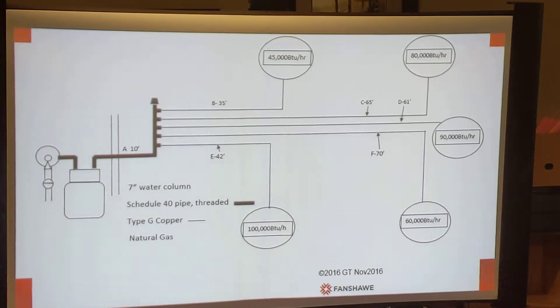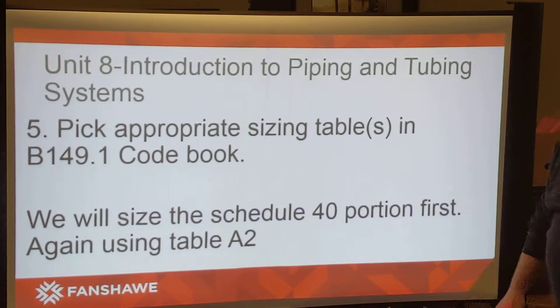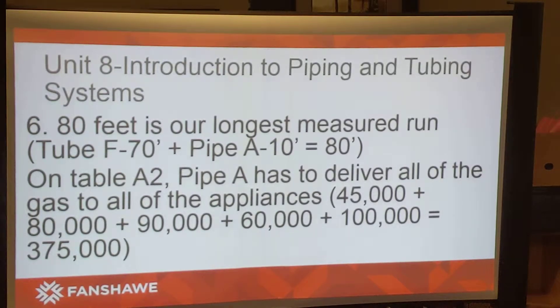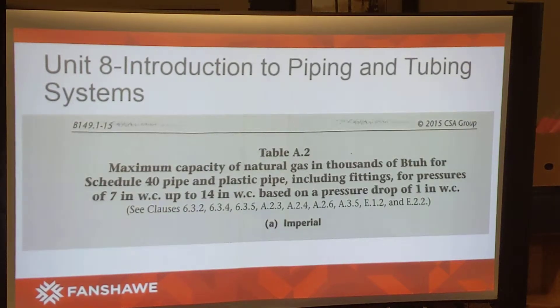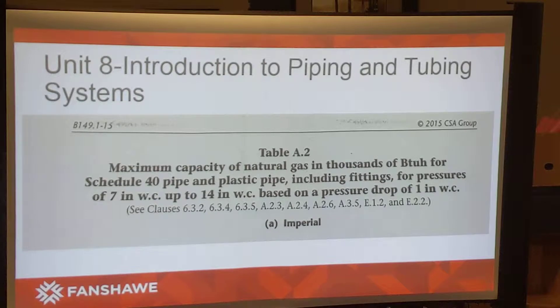We're going to pick the appropriate tables as indicated in the B149.1 codebook. The first portion we're going to size is the schedule 40 portion, so we're going to use Table A2. Table A2 indicates the maximum capacity of natural gas in thousands of BTUs per hour for schedule 40 pipe and plastic pipe, including fittings, for pressures from 7 to 14 inches water column based on a pressure drop of one inch water column.